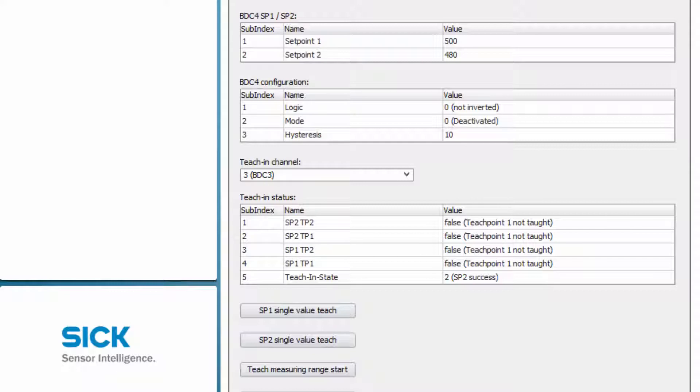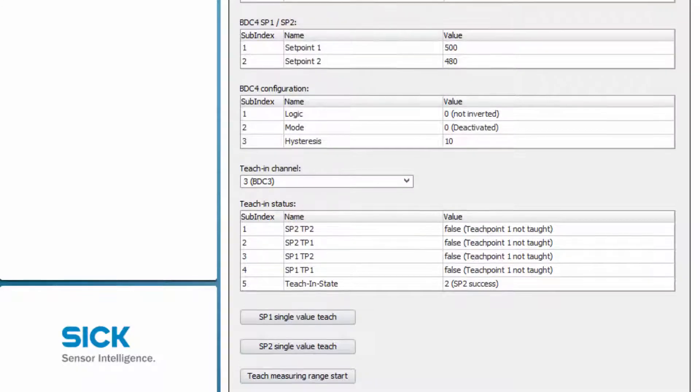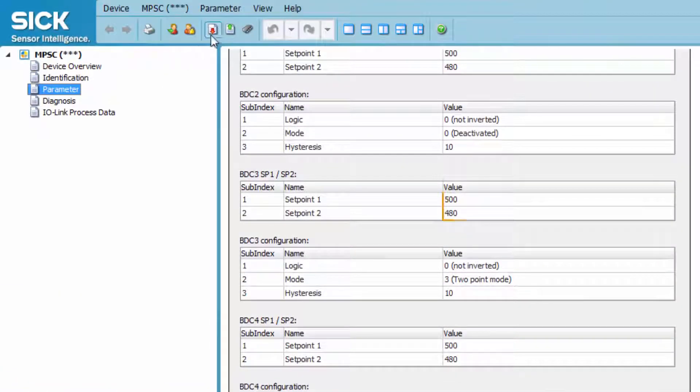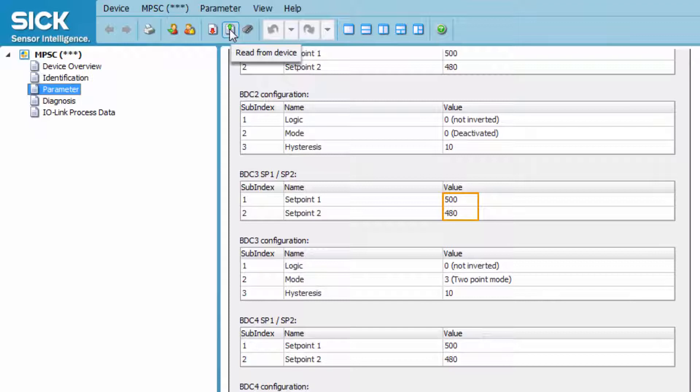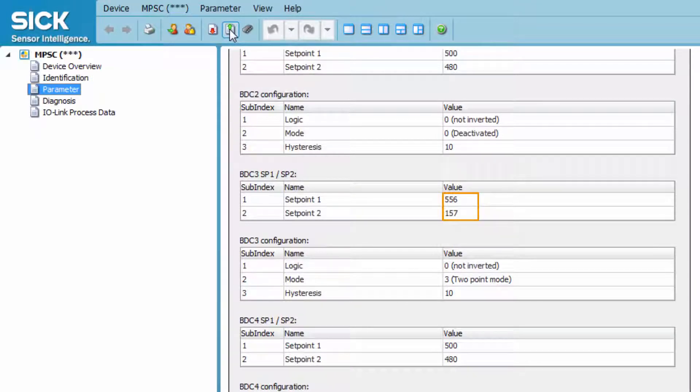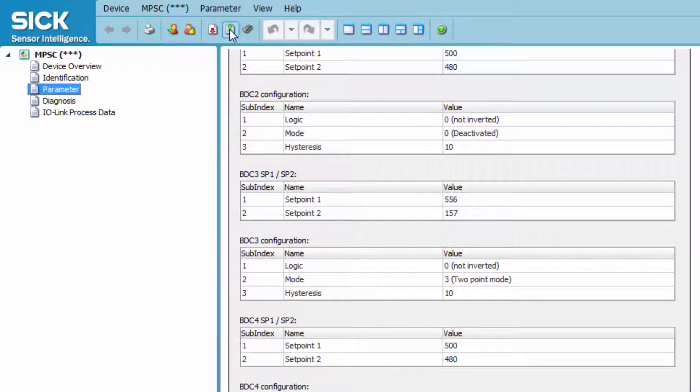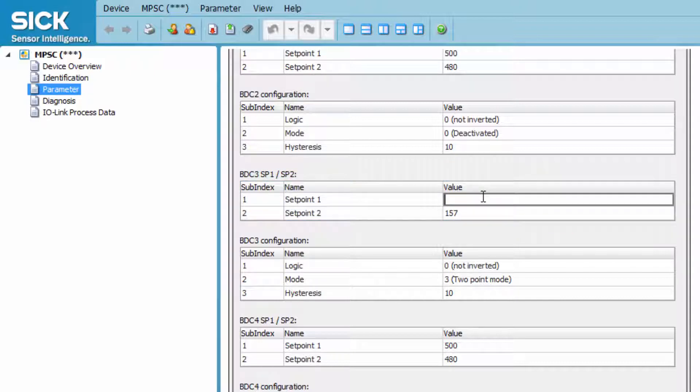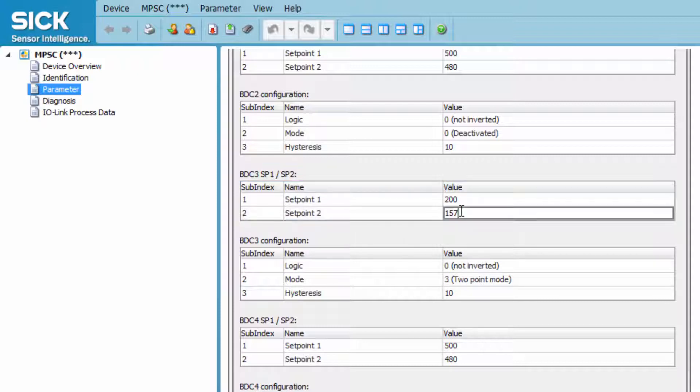To see the set values, click the Read from Device button and the two set values are displayed in the BDC3 section. The values can also be set manually. For doing so, just click in the set point 1 field of the respective BDC and enter, for example, 200. The same applies for set point 2. Enter the value 300 in this example.